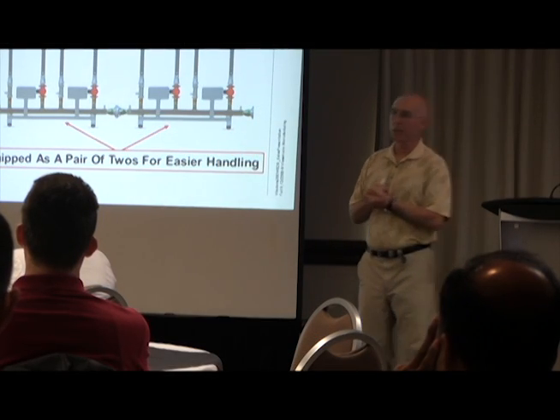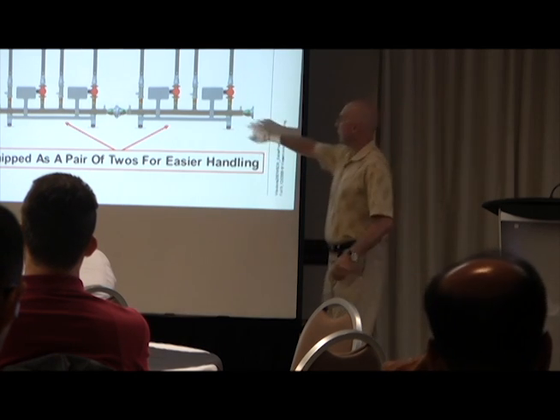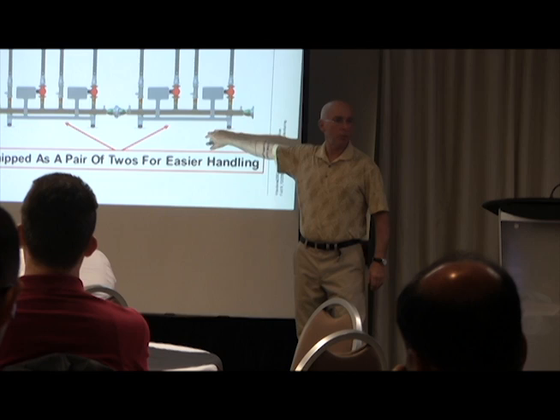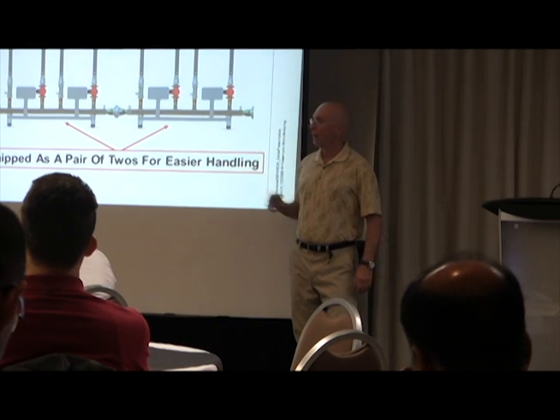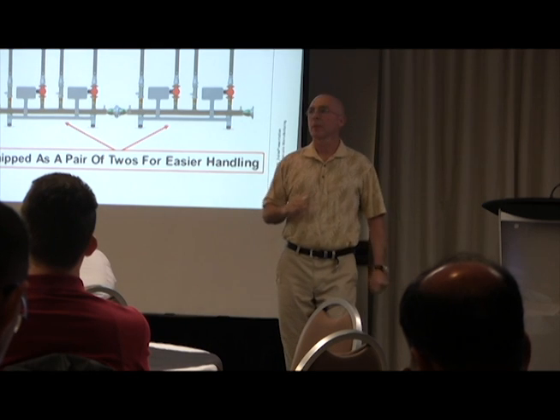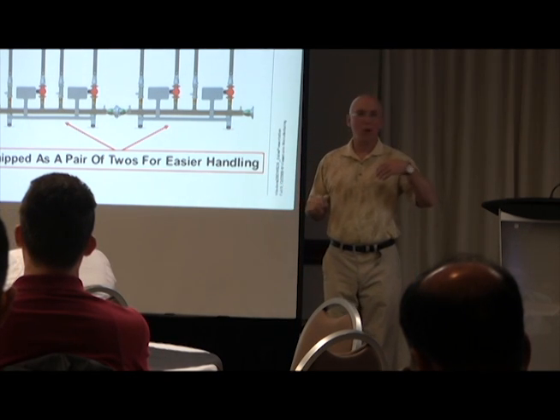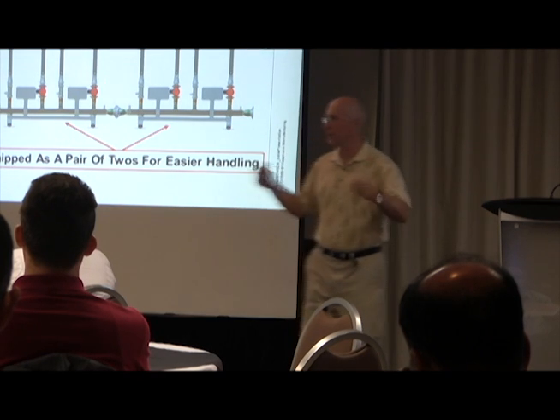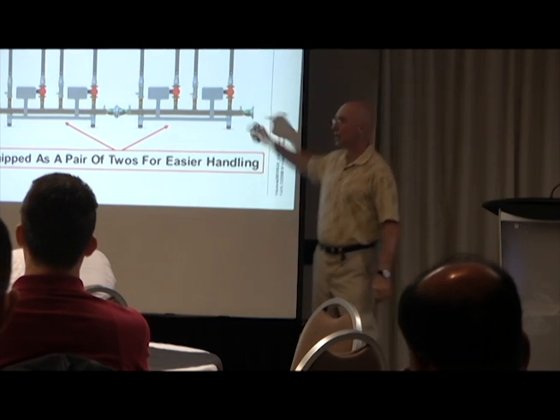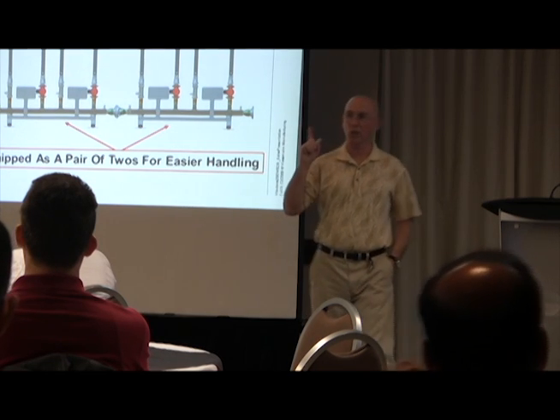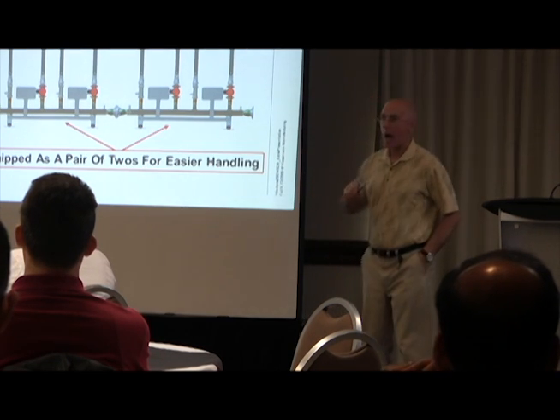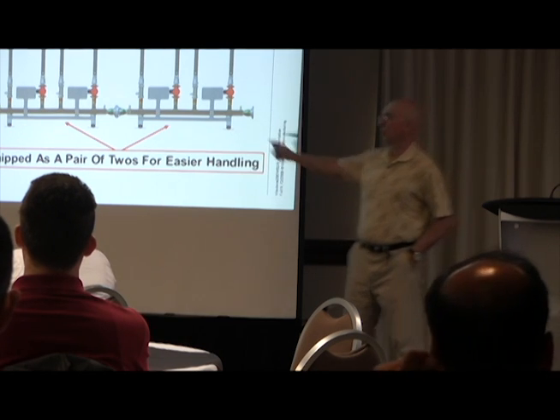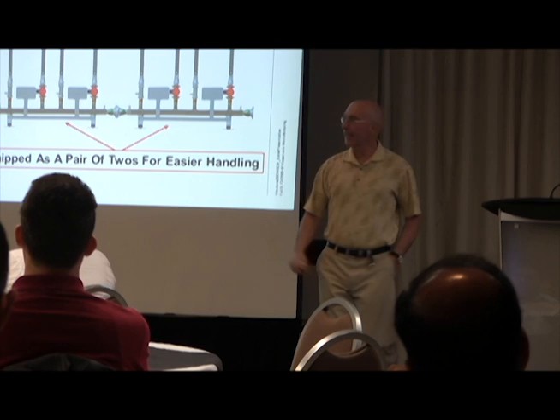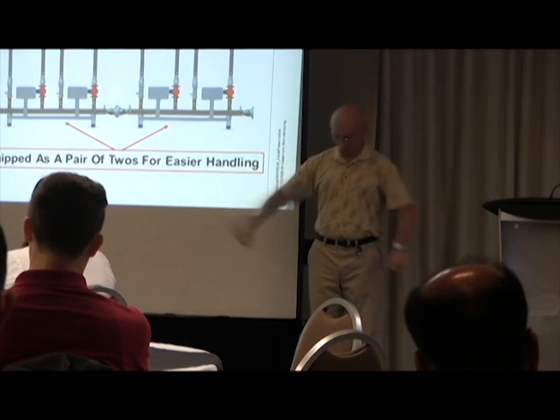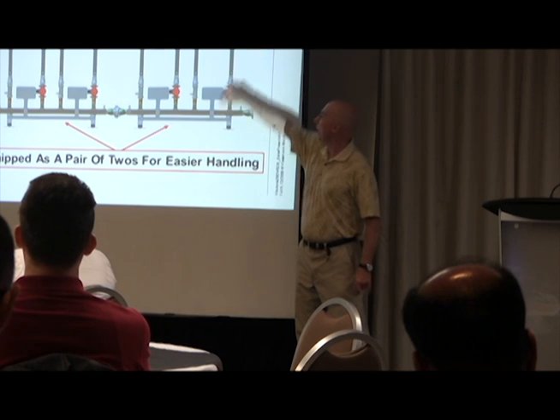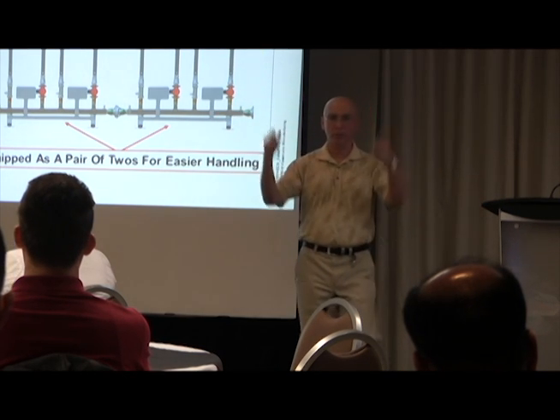Feedback from the field on this is incredible. There is a cost to the racking system, no doubt about it - there's the cost of the low loss header - but usually you get this more from the contractors than anybody else: once they use this thing once, the feedback is it took 1/10 of the time to install the product than it normally would. Basically, you bring the racks in, mount them on the floor, hang the boilers, and everything connects up underneath. It's just boom, boom, boom.